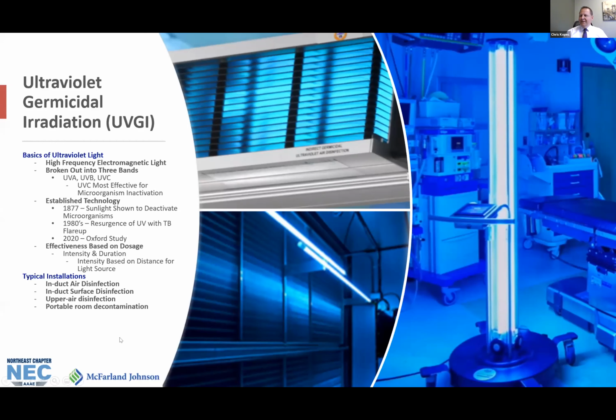So what's the best system for you? It depends on your specific equipment and situation. In my opinion, the most bang for your buck is in the cooling coil section of your air handling equipment, assuming you have enough room for the installation. So with that location, you're keeping the cooling coil clean and running most efficiently, and you're getting the added benefit of treating the air as it passes through that section. So the duration time on this is limited because the air is moving at a pretty good clip through the air handling equipment, and the intensity is high though based on the close proximity to the UV source.